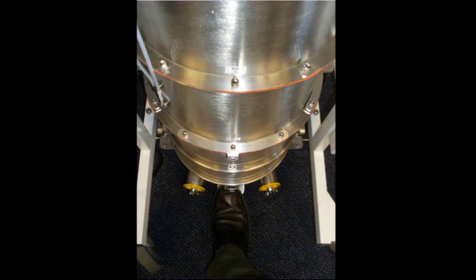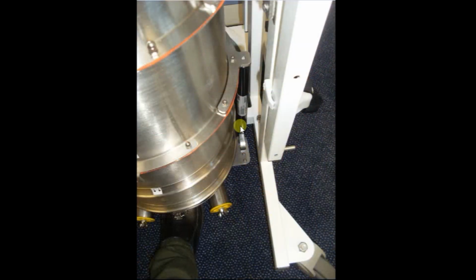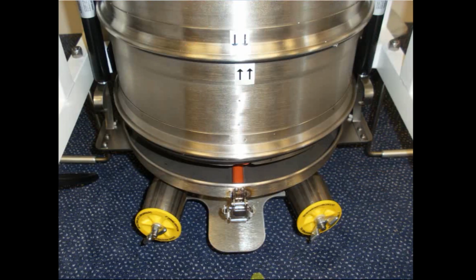Once all 3 clasps have been released, then place your foot on the foot plate as shown here and push down. Push down until the leaf springs slip under the hydraulic rams and stop them going back, stop the soda lime tray going back up. Make sure you do this on both sides, and then you'll have the soda lime in this tray in this position. Here we are, the tray is open, the leaf springs are slipped under the hydraulic ram here and under the hydraulic ram here, and we can now pop this by giving it a little sharp tap because it's stuck to the rubber here. Tap it here, the soda lime tray will drop down and can be removed. When it's removed, it looks like this.